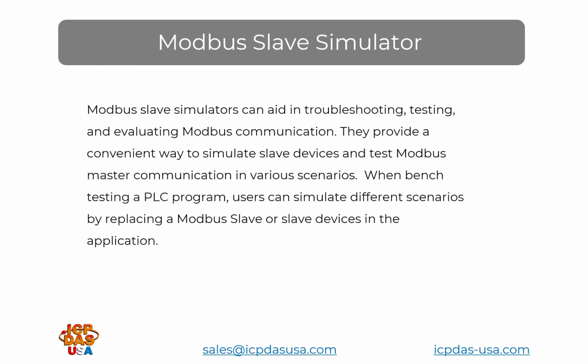Unfortunately, we do not provide a slave simulator, but there are many out there. Two that come to mind are the ModRSsim and the CSCS simulator. These can be used with our TM7561 to simulate a slave connection to your Modbus master. In instances where the slave devices have not arrived yet or you are doing a pre-installation simulation, slave simulators allow you to simulate data from slave devices and test programs and actions.